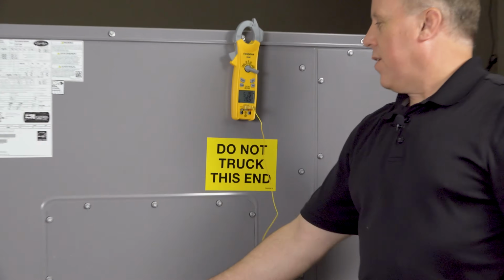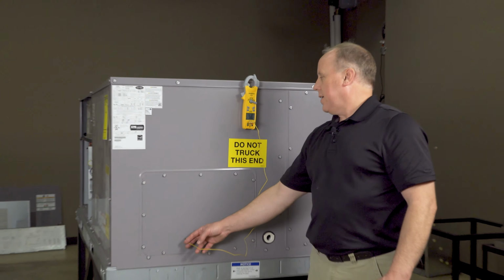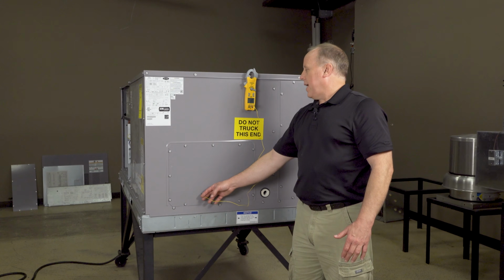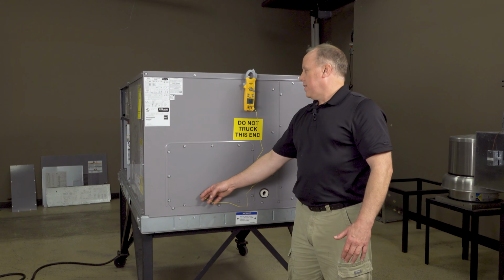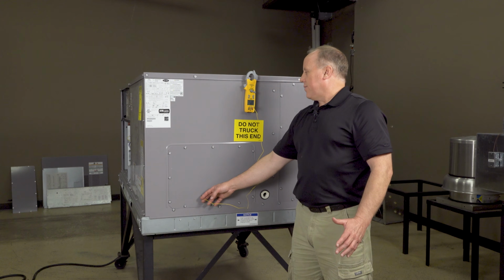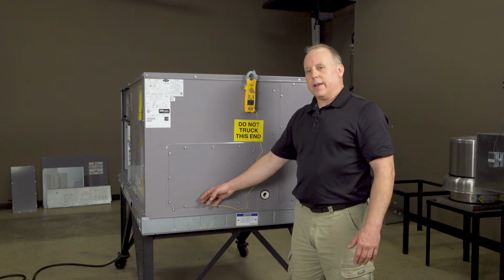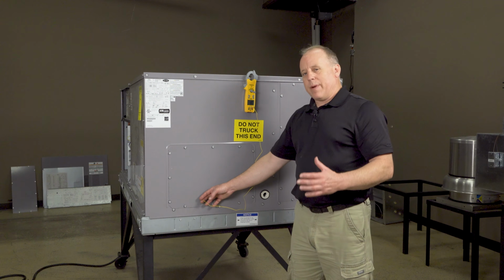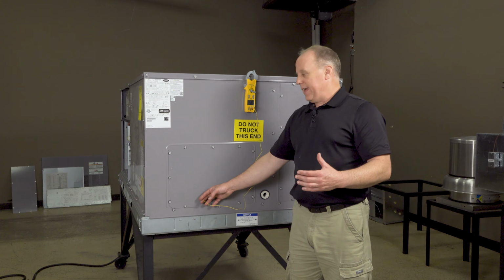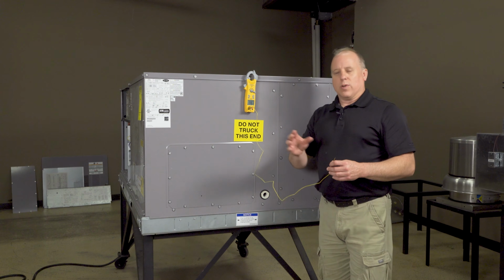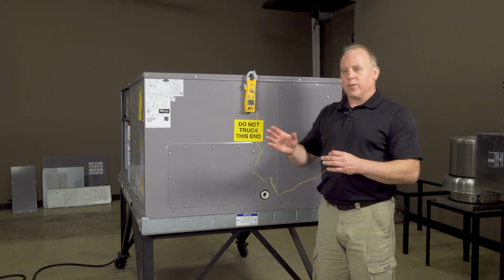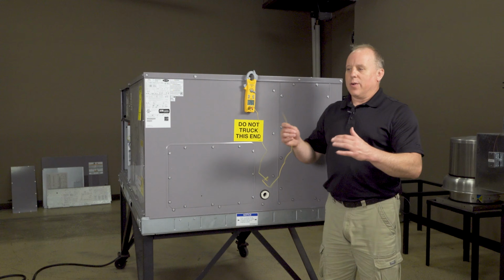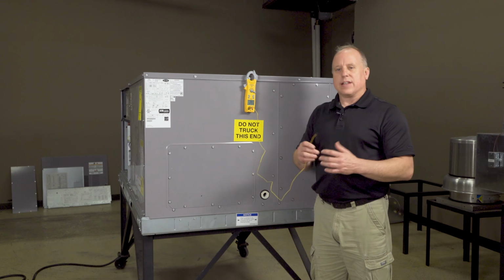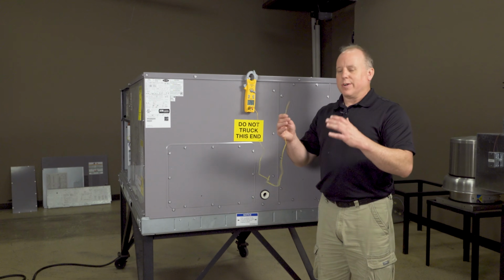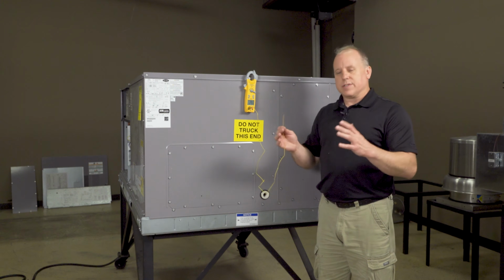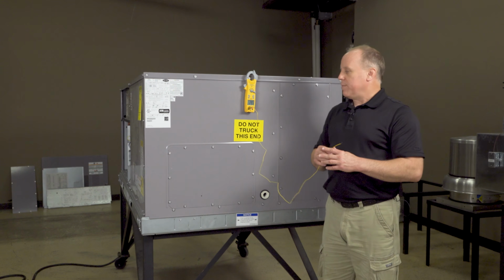So we're only showing a 51 degree supply air temperature. It's dropping to about 50, between 50 and 51. So right now we only have about an 11 degree drop on our AC. Normally on AC, we're looking for somewhere 18 to 20 degrees, roughly. Slightly less than that is okay. Ideally that temperature, 18, 19 degrees, that's kind of a good spot to be at.